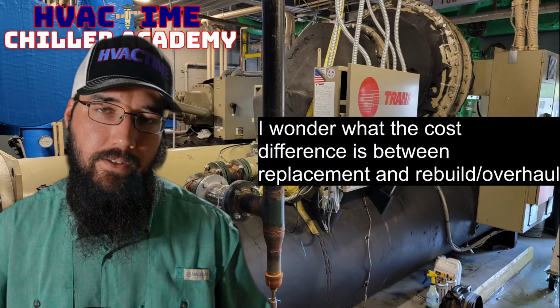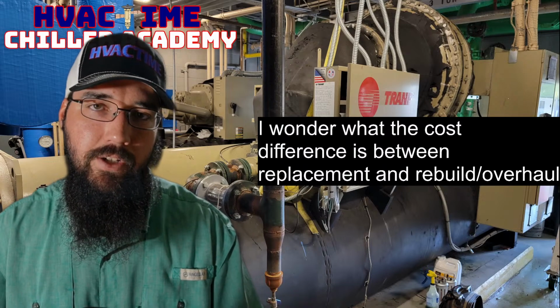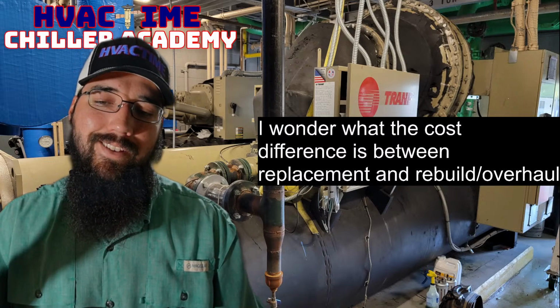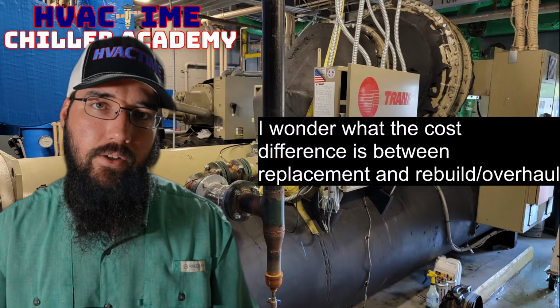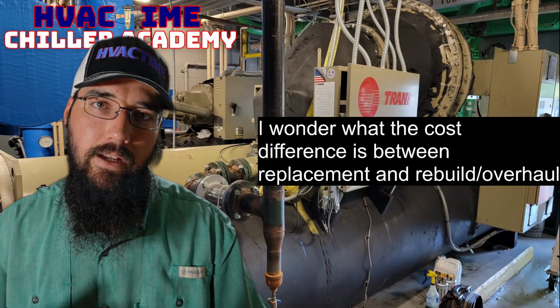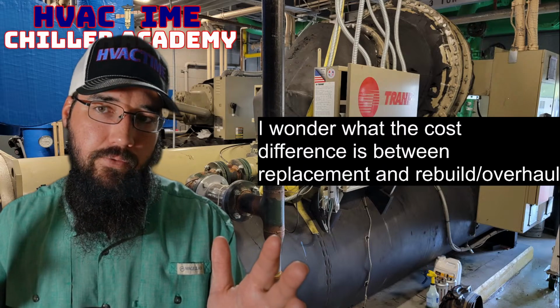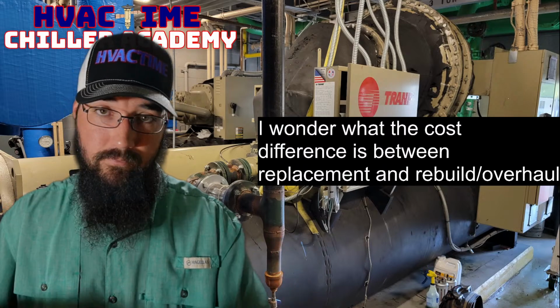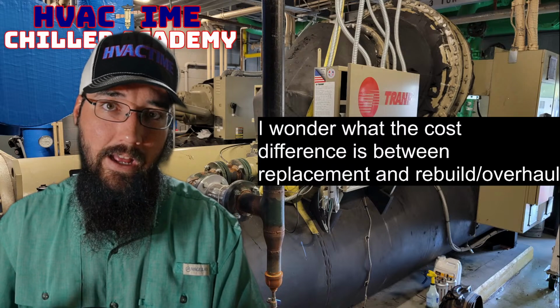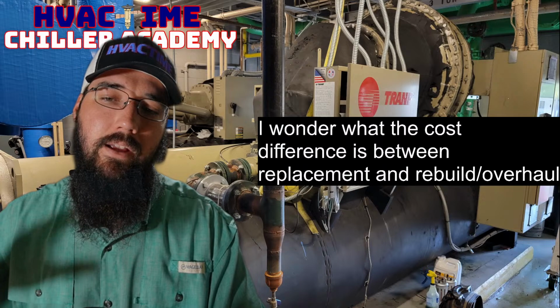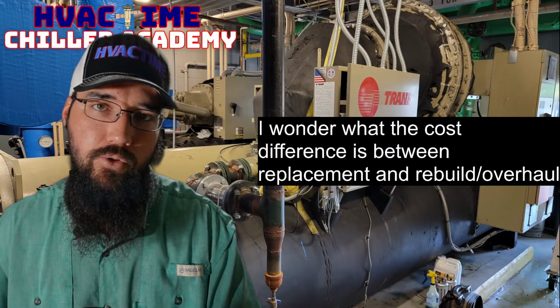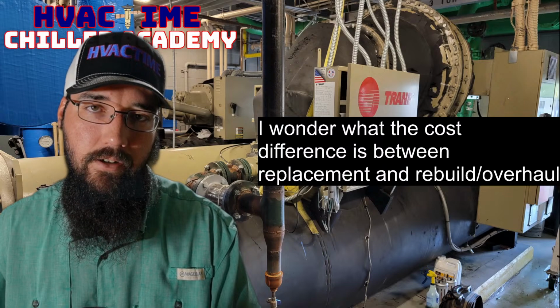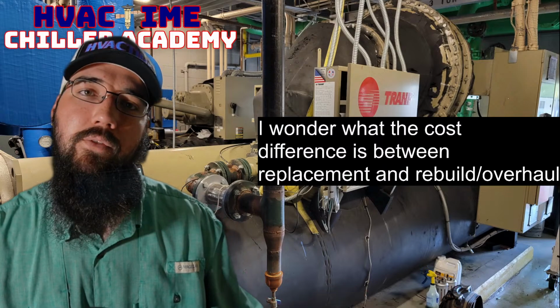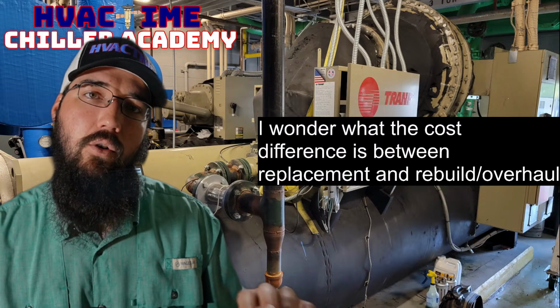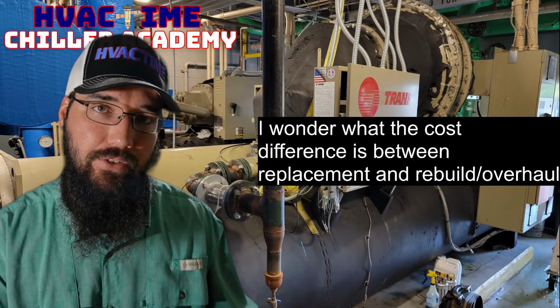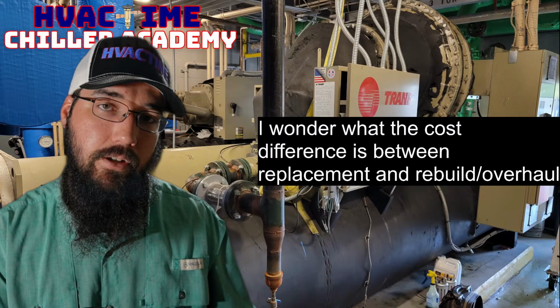It's been my experience that the larger the machine gets, the more true this becomes: the time and cost required to get a new chiller, especially when this chiller is already down, dead in the water, and needed now, is significantly higher than the turnaround time and cost for the overhaul. With the overhaul, we can get this machine back online faster and cheaper.